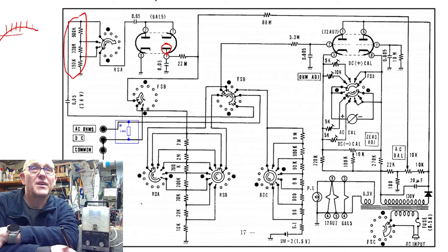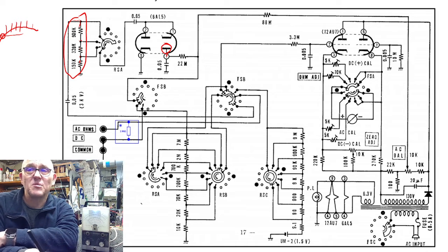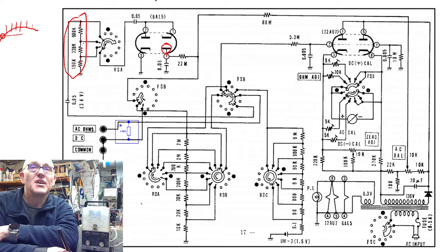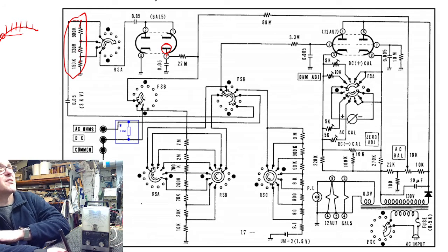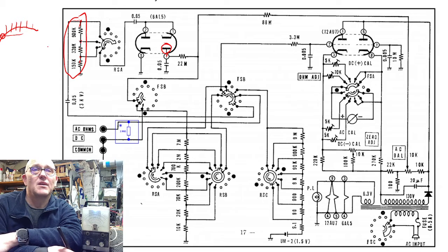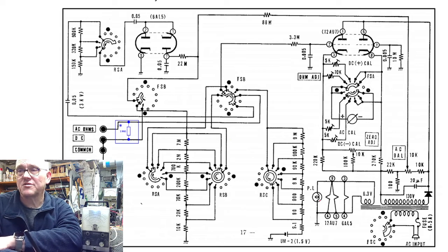You understand what I'm doing? I like this linear portion so I can get a nice linear DC representation of the AC voltage coming in. So when the voltage gets too high, it gets pre-scaled through these resistors depending on the range that's being selected. So that'll be, for example, 1500 volts, 500 volts, and the pre-scaling will stop at 150 volts, to prevent this anode saturation and the loss of linearity at this point. What else is there to do?